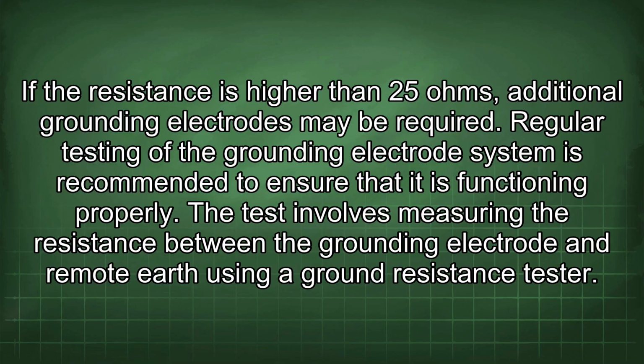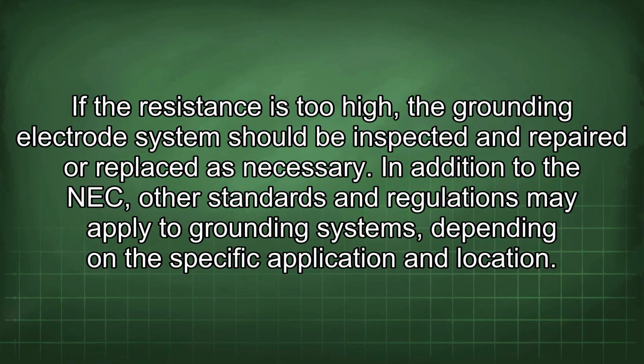Regular testing of the grounding electrode system is recommended to ensure that it is functioning properly. The test involves measuring the resistance between the grounding electrode and remote earth using a ground resistance tester. If the resistance is too high, the grounding electrode system should be inspected and repaired or replaced as necessary.